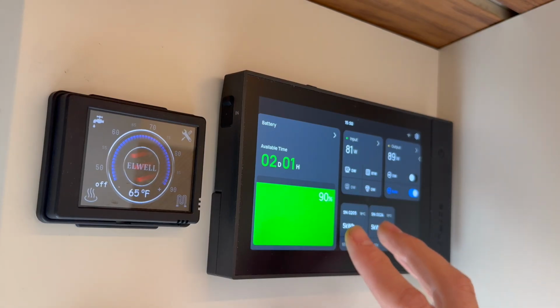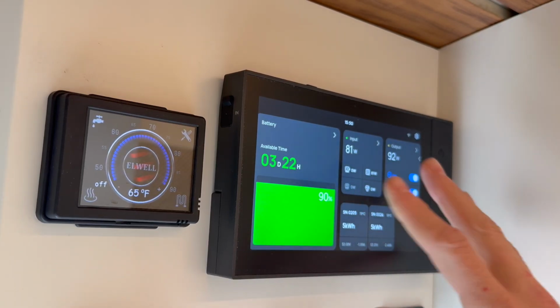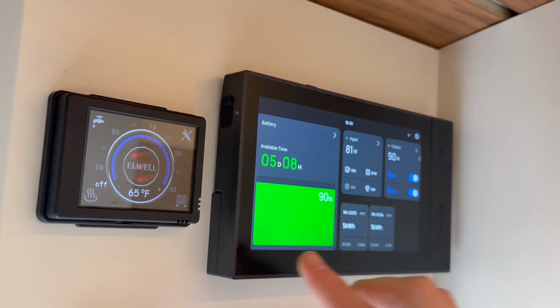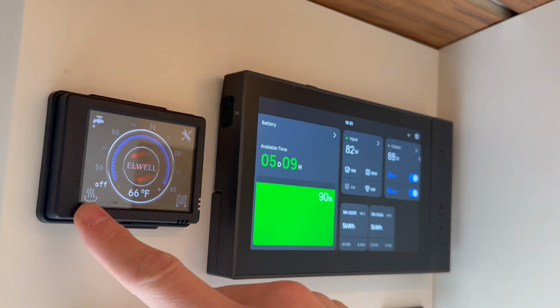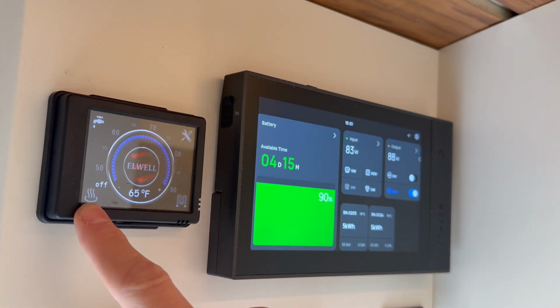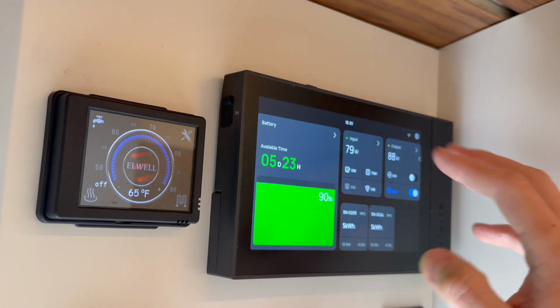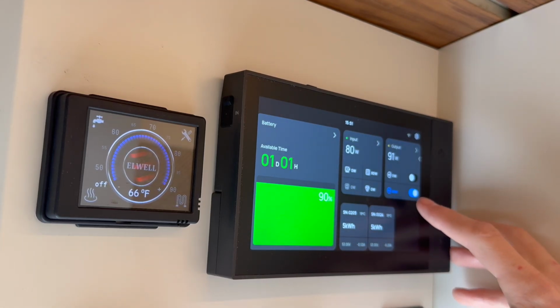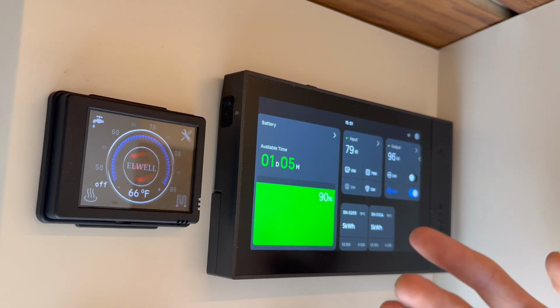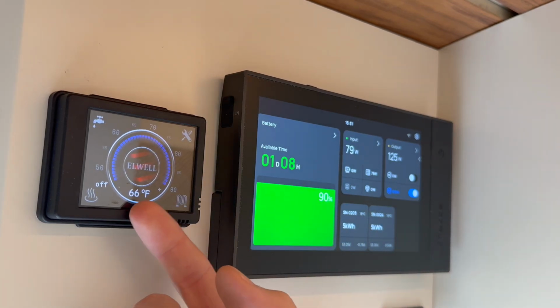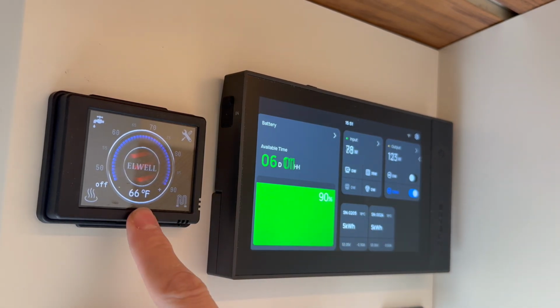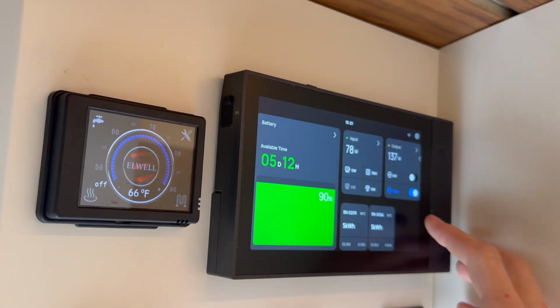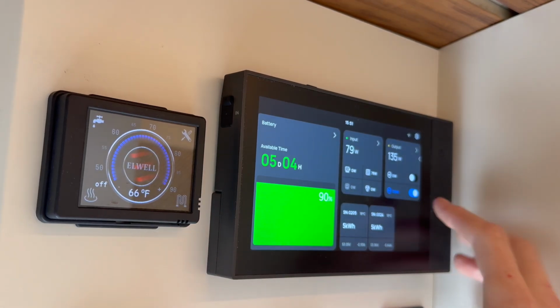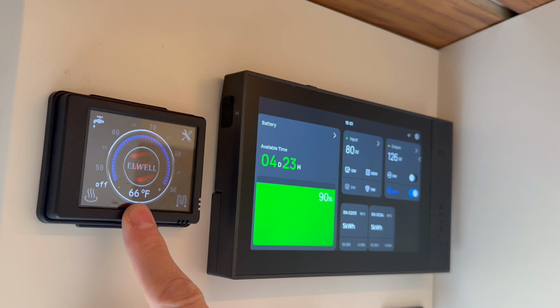Another thing that's important, clients wanted to put their van away for a few days, but it was freezing outside. So they left the heater on the burner, so on this button, but before leaving, they turned off the DC power to save battery in the van. Well, even though your heater does work on the fuel tank, the monitor runs on DC power. If you turn off the DC circuits, your heater will turn off and your van is in danger of freezing if it's cold outside.